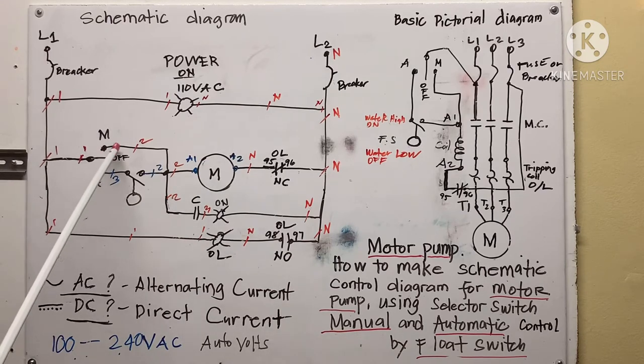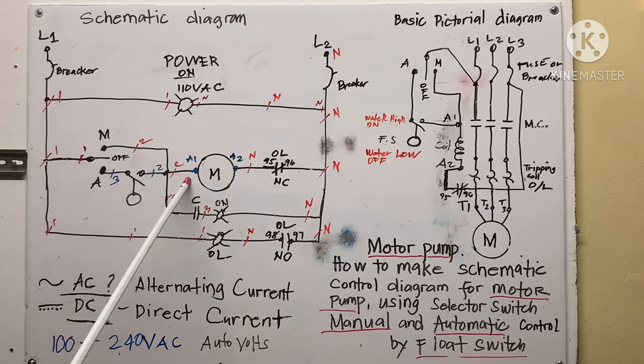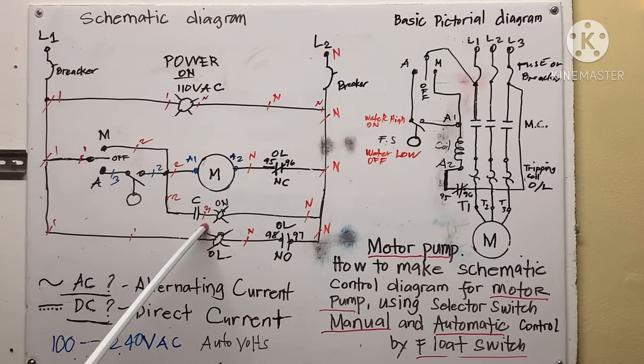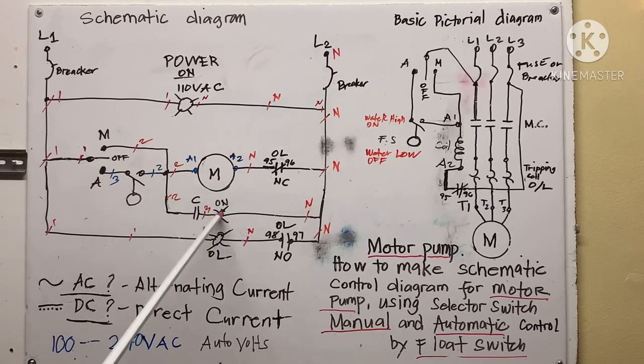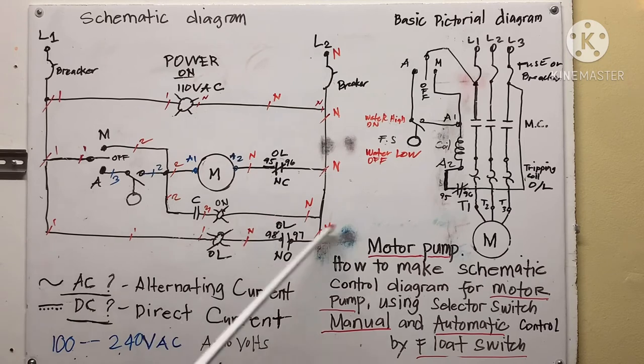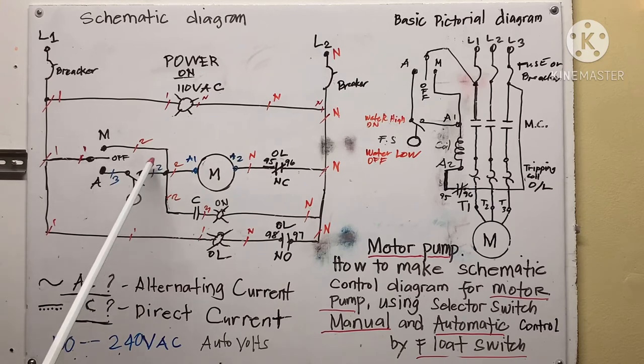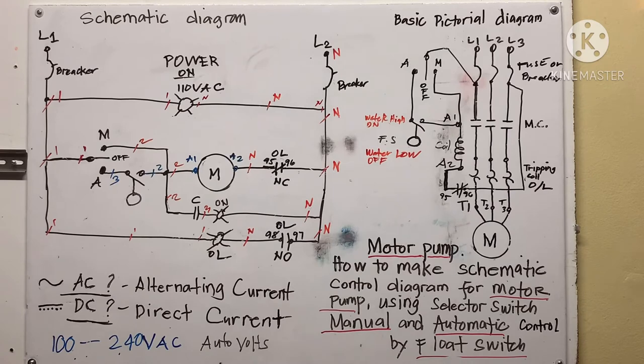Number two goes to A1 of the magnetic contactor, and also to the normally open contact of the magnetic contactor, going to the indicator light — so I put number two there as well. Number three is used for the next node. So we only use three numbers — one, two, and three — because all the neutral is already connected.